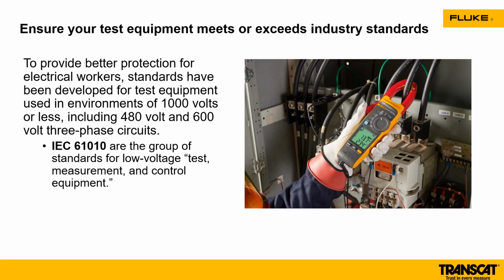You also want to make sure that the meter is part of the IEC 61010 guideline, the standard for equipment on these low voltage meters. Now, when I say low voltage, that's 1,000 volts and less. But make sure that your tool is rated correctly. Part of that is your category ratings. We want to make sure that the meter can actually handle the category environment at that 1,000 volts, or maybe it's 480 volt 3-phase that you're working with, because voltage out there can have problems.